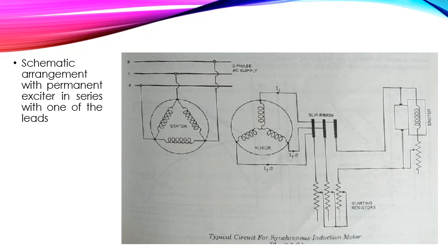So there are some drawbacks or limitations of this motor, that is extra cost and low efficiency as compared to that of the standard types of induction motor, and there is a small space for copper with a distributed rotor winding. That's why a compromise has to be made between the excessive ring voltage at starting or excessive rotor current during the operation. So these are the limitations.